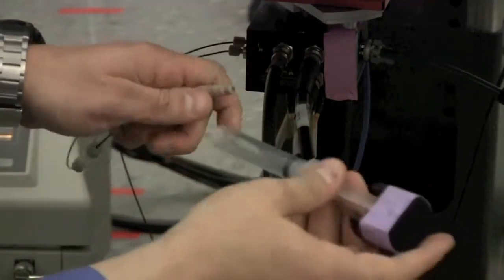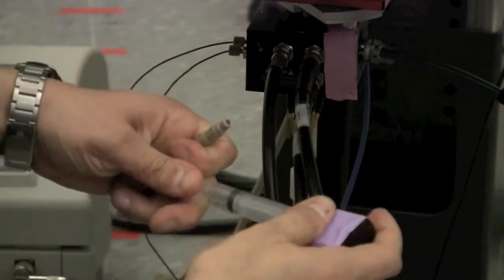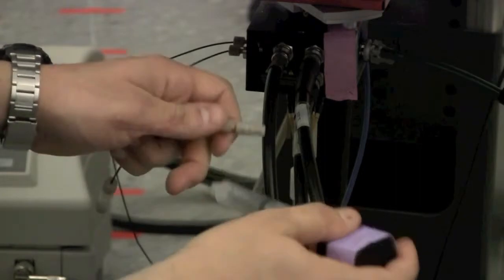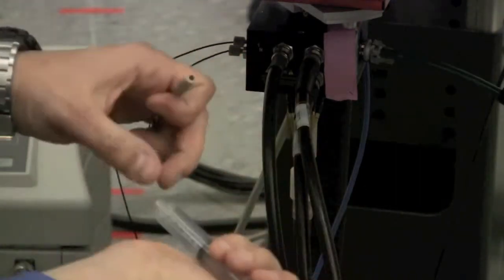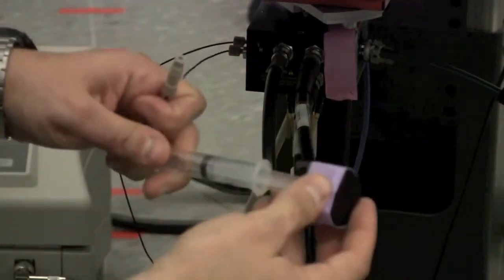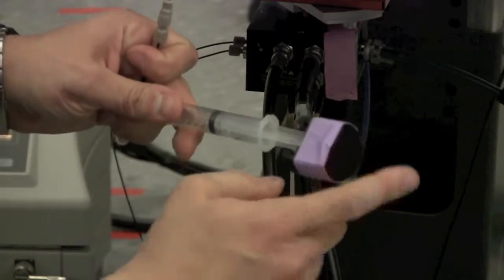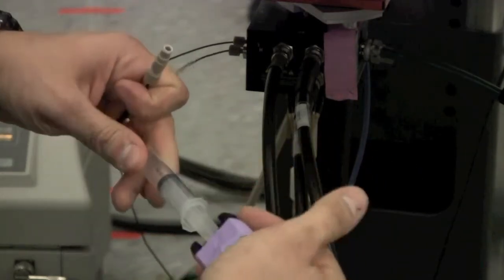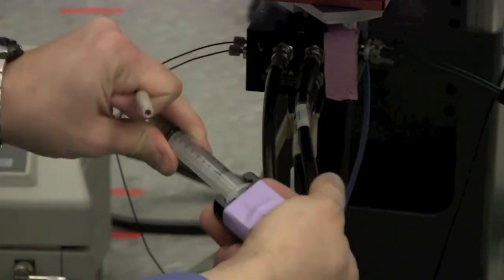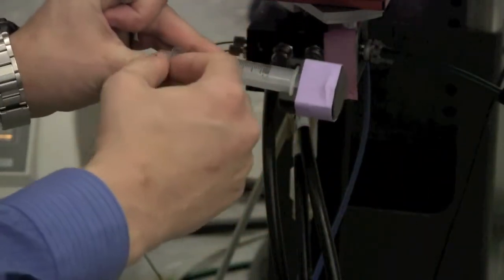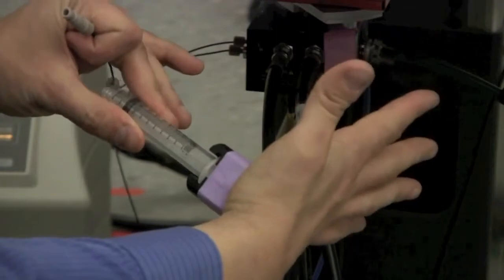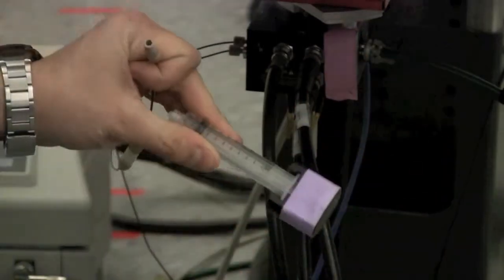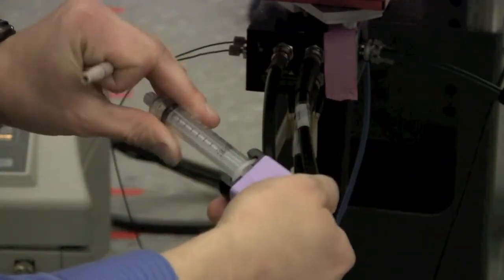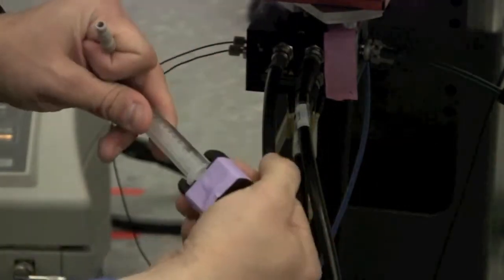When you're using this one, make sure never to draw it up while it's attached to the system, because we don't want to suck solvent back into the syringe. We want to keep the syringe as clean as possible. And this kind of funny thing on the end here is to allow us to push it down and lock it into place, because when we push in the air, it's going to build a lot of pressure, but we'd have to hold it in for a long time in order to push all the solvent out. So this will allow us to lock it into place, and then we don't have to hold it.